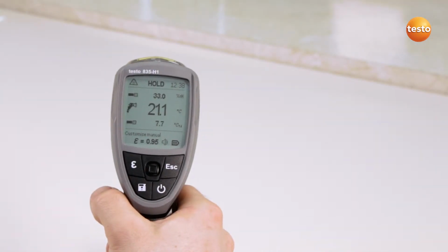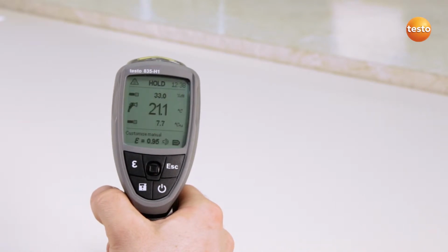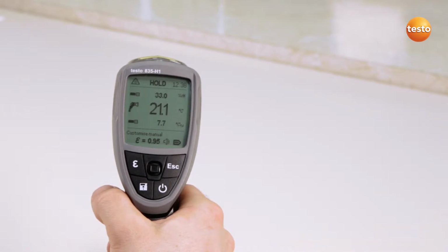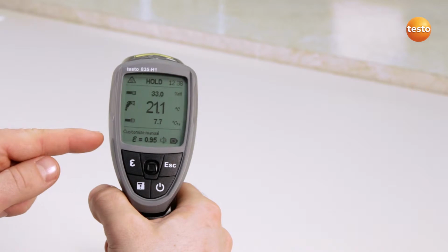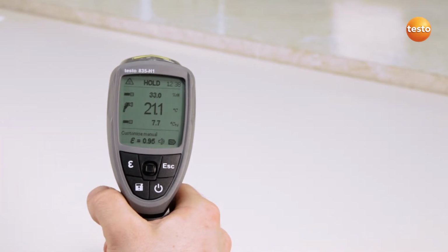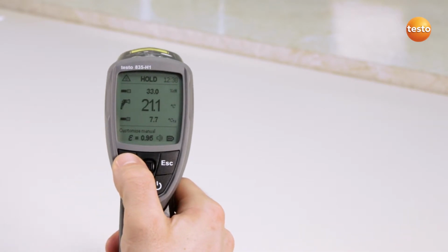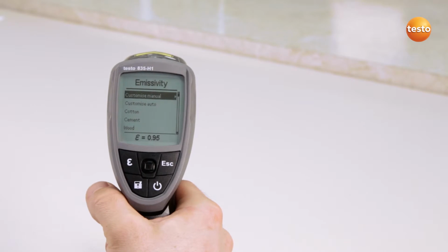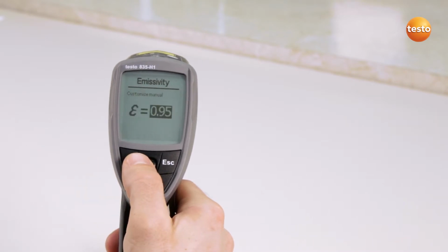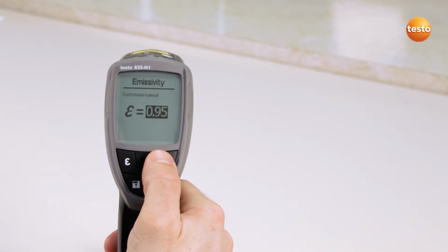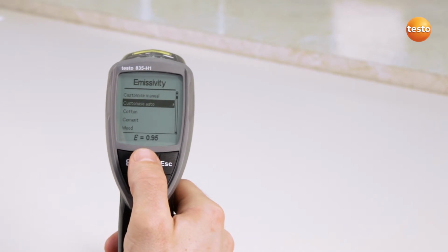There are several possibilities for obtaining even more accurate measurement results and for adjusting the Testo 835 measuring instrument to the emissivity of the measurement object. The instrument is delivered with a basic emissivity setting of 0.95. You can, of course, adapt it according to your measurement environment. First, call up the emissivity menu. Here you can adapt the emissivity either manually, automatically, or via preset guideline values for various measurement objects.